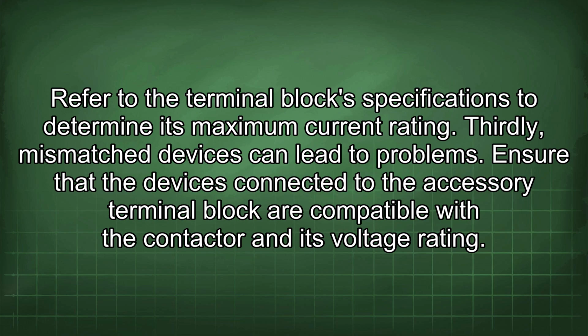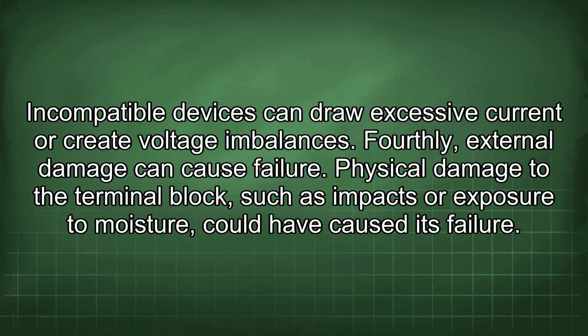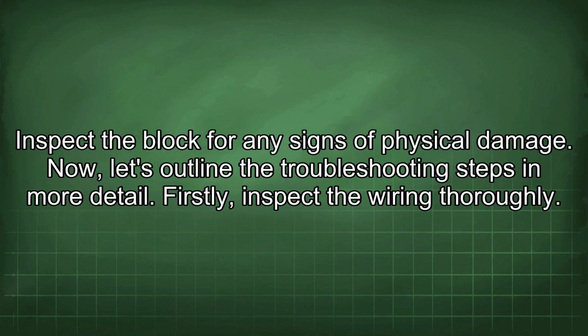Thirdly, mismatched devices can lead to problems. Ensure that the devices connected to the accessory terminal block are compatible with the contactor and its voltage rating. Incompatible devices can draw excessive current or create voltage imbalances. Fourthly, external damage can cause failure. Physical damage to the terminal block, such as impacts or exposure to moisture, could have caused its failure. Inspect the block for any signs of physical damage.